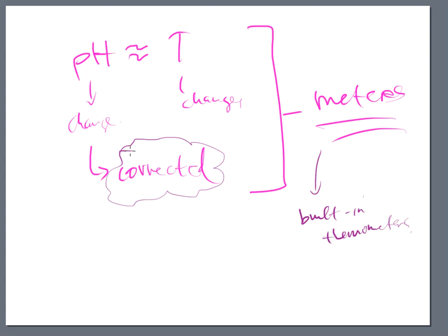The meter does the math for you based on the temperature and the voltage you provided, and pops out a number. The pH reading you get on the meter is very often already self-corrected.